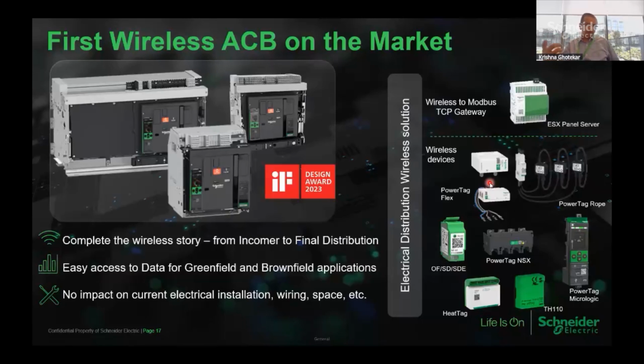So as I said, this is the first wireless ACB on the market. Similar to other wireless devices we have, for example, we have HeatTag, which are thermal sensors on the panel. PowerTag, you can put it into the circuit breaker. We have a wireless OF for the Compact NSX circuit breaker, where you can put it and it will send the status, on, off or trip indication, wirelessly to the gateway.